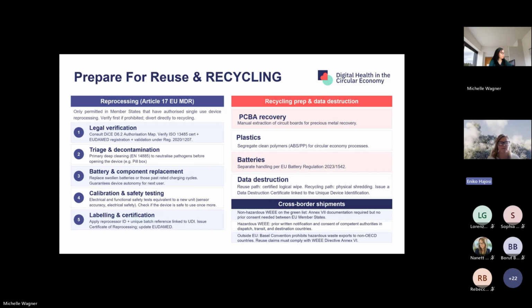Then comes the triage and decontamination phase, where the device is assessed and cleaned to make sure that any biological risks are removed. And this is, of course, according to relevant standards. After which there may be a need to replace certain components. Particularly, we are talking about maybe batteries or other parts that might degrade over time. And once that is done, the device has to go through calibration and safety testing to make sure that it works according to the required standards.